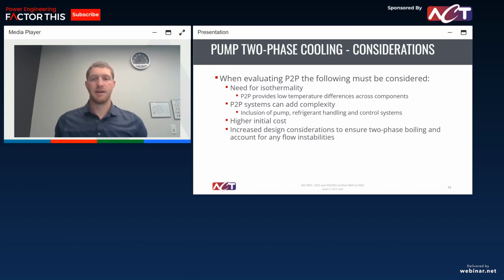There's extra time in design, extra time making sure that for your two-phase boiling, you're accounting for any flow instabilities. That can certainly be a challenge in design, but during operation, since you're running your pumps a lot slower, or you have much smaller pumps, you should hopefully have less power consumption. You oftentimes will have less maintenance on a pump two-phase loop as opposed to single phase. So even with the higher upfront costs, you'll oftentimes make that cost back during the operation of the system.